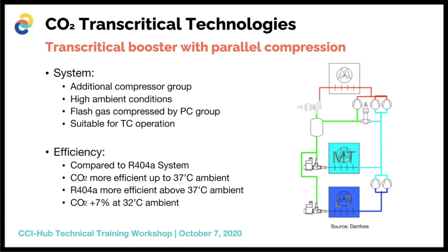Comparing to R404A, the parallel compression system makes CO2 more efficient up to ambient conditions of 37 degrees Celsius, which covers most countries around the world. At the 32 degrees Celsius set point, CO2 with parallel compression can achieve up to seven percent energy efficiency gain compared to an R404A system, and sometimes even higher depending on the installation and setup.